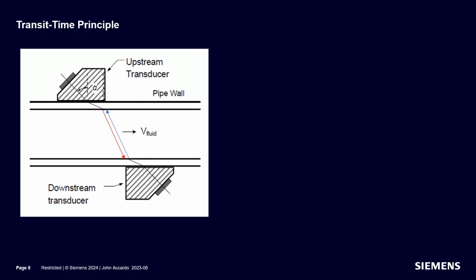You have two transducers on the pipe, and an ultrasonic wave is sent from one transducer into the pipe wall, then through the fluid stream, through the other pipe wall to the receiving transducer. And that goes in both directions. So one transducer is a transmitter, the other is the receiver. One sends a sound beam to the other, and then they reverse roles. What was the receiver now becomes the transmitter and sends a signal back the same exact way, opposite direction, same path length, same frequency, same everything.